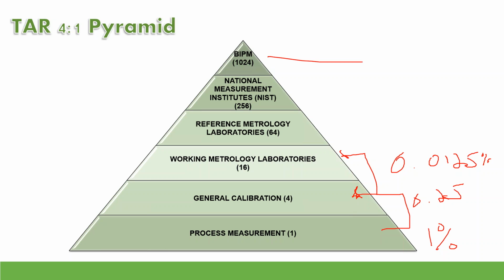So at the end of the day, in this scenario, does that 1% measurement down here, if we make it the whole way up to a National Measurement Institute, is NIST really going to be 256 times better? And then if we go back to the SI, at the BIPM level, is it really going to be 1,024 times? It's just impossible to maintain. In a confined system, this is very containable.